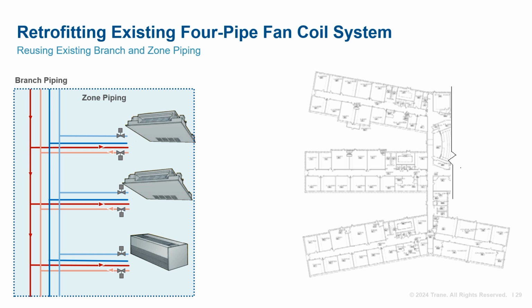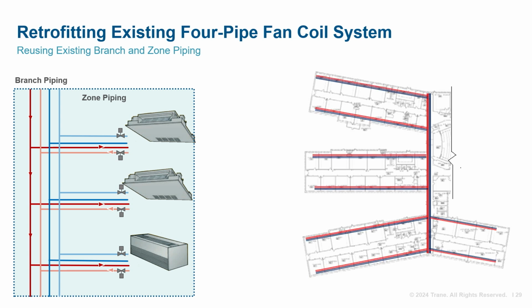To illustrate, let's consider a common architectural design known as a finger school, characterized by classroom wings branching off from the center of the building. This building has existing 4-pipe distribution with fan coils or unit ventilators in each classroom. At the center of the building, there is a central chase with large distribution piping. Each classroom wing has 2 sets of branch piping for each facade. This is sized for 44-degree chilled water and 140-degree hot water. Each branch then feeds 8 to 10 zones with 4-pipe connections to the fan coils or unit ventilators.